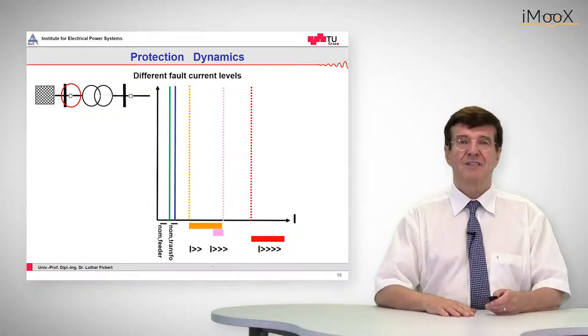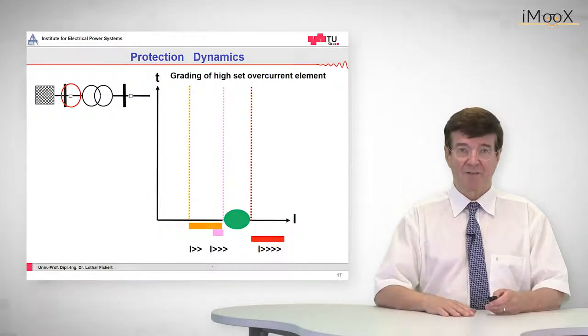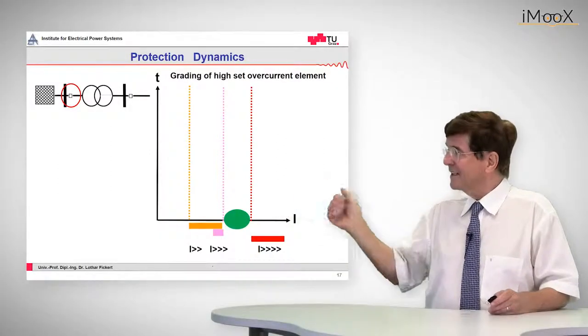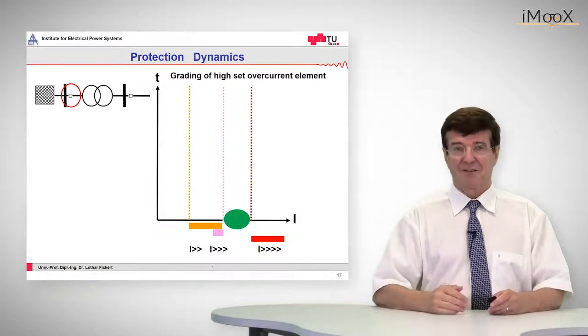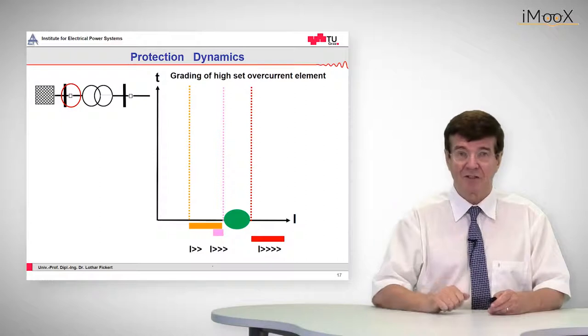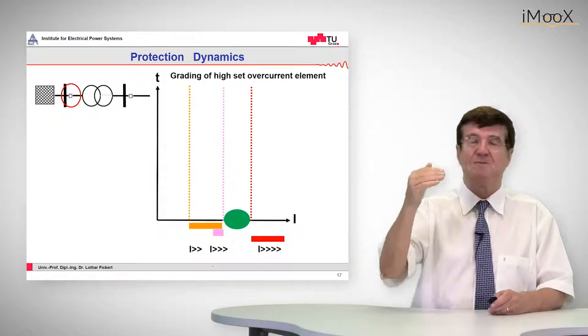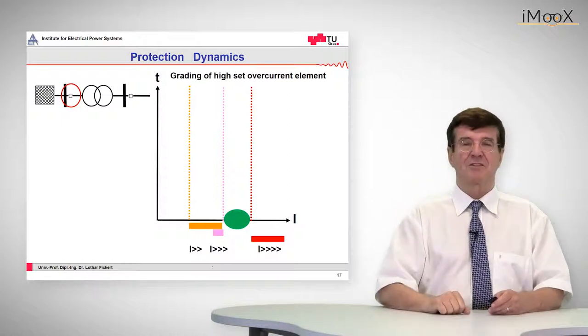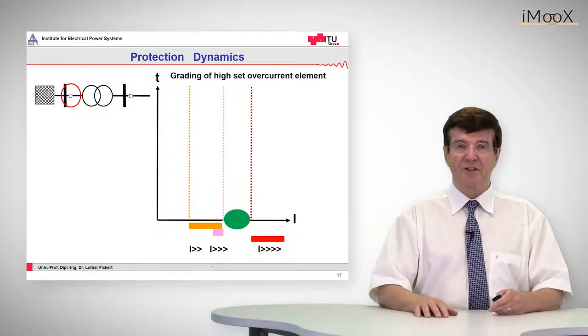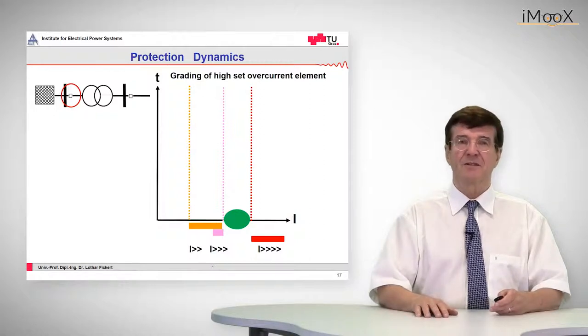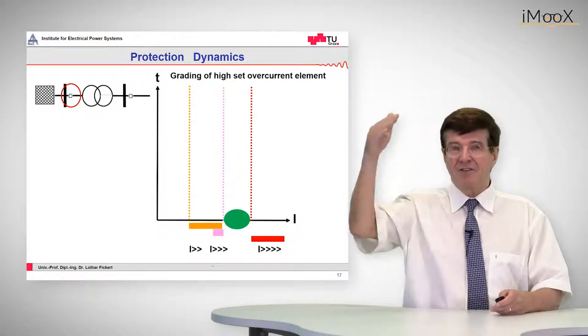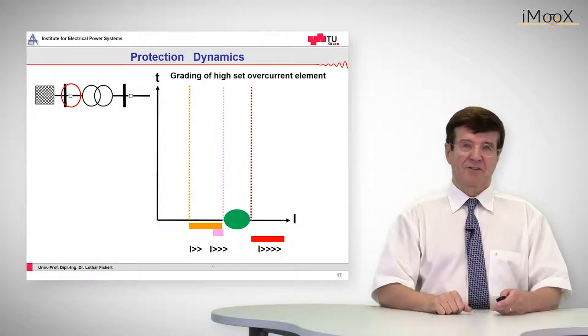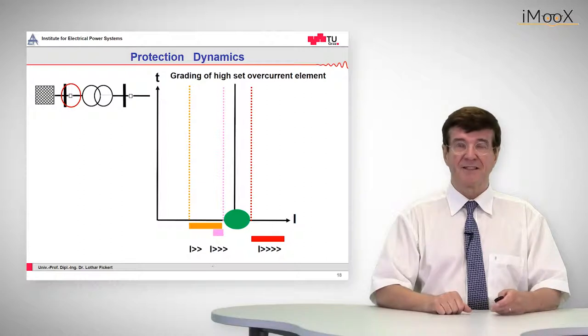Now let's see how to set the high set element of the transformer protection. As we can see, there is a current gap between the fault current level at the high voltage side and that on the low voltage side. So either the current is high — meaning the fault must be on the high voltage side — or it is low, meaning it must be on the low voltage side, and that can be used for discrimination. We concentrate on the green circle, which is a zone where there is no fault current, and this zone can be used to discriminate between high voltage side and low voltage side short circuits. We can set the pickup value of the high set element within this zone.